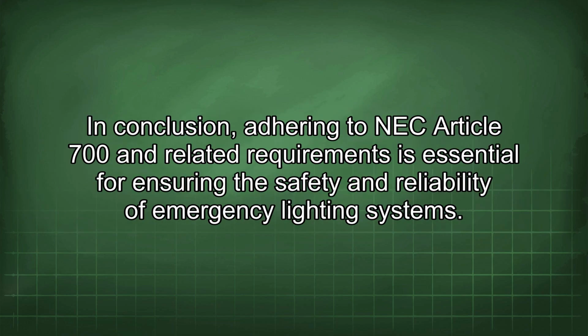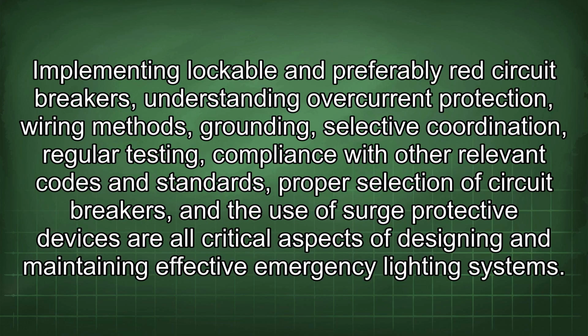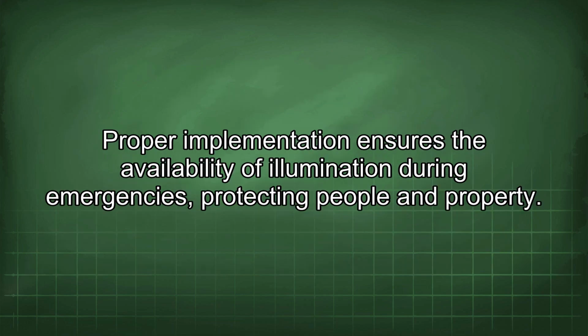In conclusion, adhering to NEC Article 700 and related requirements is essential for ensuring the safety and reliability of emergency lighting systems. Implementing lockable and preferably red circuit breakers, understanding overcurrent protection, wiring methods, grounding, selective coordination, regular testing, compliance with other relevant codes and standards, proper selection of circuit breakers, and the use of surge protective devices are all critical aspects of designing and maintaining effective emergency lighting systems. Proper implementation ensures the availability of illumination during emergencies, protecting people and property.